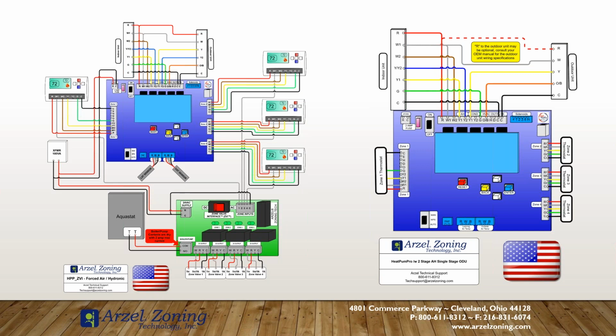We go over it a little bit more with zoning specific diagnosis rather than low voltage diagnosis. But on all of our panels, the solenoids have a terminal marked plus, and you'll notice that there are multiple wires in those plus terminals. That's common. If you were to disconnect those plus wires, so you pull them out of the terminal, every solenoid is de-energized, and it doesn't matter what thermostat's calling, every single damper in the system would remain open.